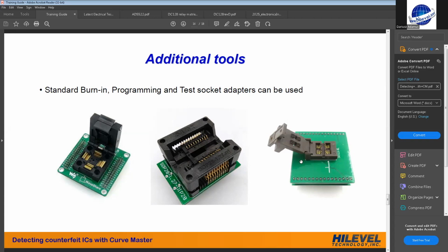And then when you compare your device under test, you compare it to this golden device, and it's compared pin by pin. So you can ideally verify every single chip if it's within the spec.